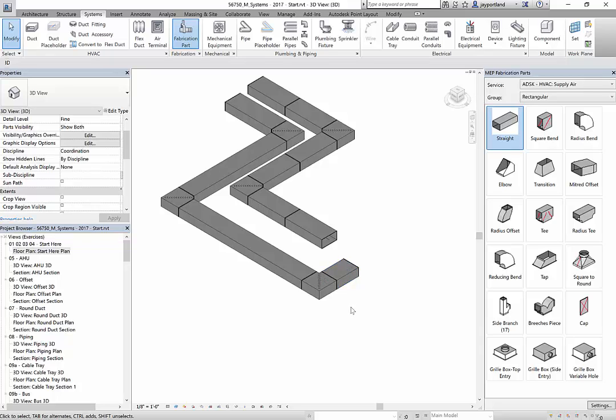So again, Revit does not have the ability with the fabrication parts to justify them on top or on the side, but you can do it with a classic ductwork command. If you have to do some odd justifications there, my suggestion is use the classic ductwork and then design the fabrication so you can get the right level of detail.